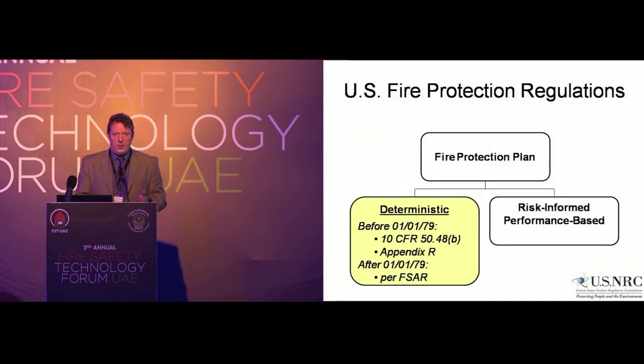Plants that were licensed before January 1st, 1979 were subject to the prescriptive requirements of 10 CFR 50.48(b) and Appendix R. These prescriptive requirements were based on an assumed serious fire where the generic criteria was established for all plants. And when we talk about deterministic requirements, we're talking about, as I mentioned before, requirements for separation of trains. It turns out to be 20 feet, or having a 3-hour fire barrier with installed detection and suppression systems.